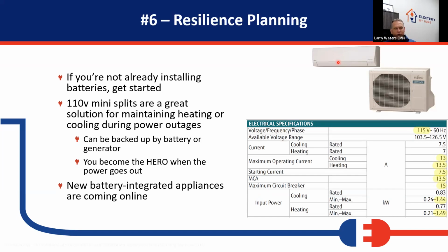So very good for older folks that don't want to take the risk of not having heating or cooling while the power's out. And at least they'll have one room as kind of a refuge. And you're going to become the hero when you offer something like this, because you can't honestly say that a traditional air conditioning system is going to run very long on batteries very efficiently and not understand the implications of how much energy that system uses and the condition of the house. So if you're putting batteries in and wanting to back up an old air conditioning system in a house that's not well insulated and the power goes out when it is really hot outside, it's not going to take long for that old clunky air conditioner to deplete those batteries and then create not too happy customers.